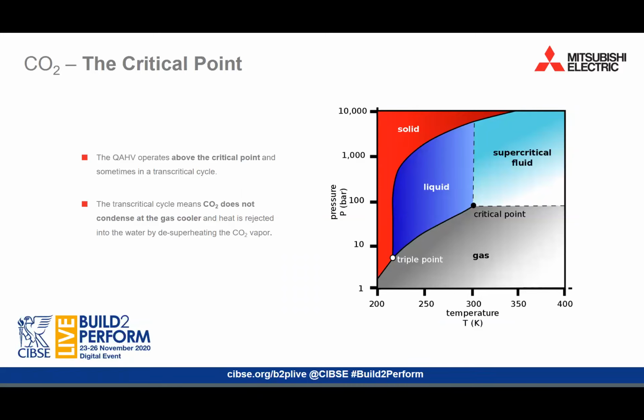So what does this low critical point mean for the operation? The critical point shown on this diagram is the point beyond which the gaseous and liquid phase of CO2 is the same density, and the CO2 vapor will not condense or change phase. CO2 in the QAHV operates above this critical point and can sometimes operate in what is defined as a transcritical cycle. This is where heat is rejected into the incoming water by cooling or desuperheating the CO2 vapor at supercritical pressure in a unique counterflow gas cooler.